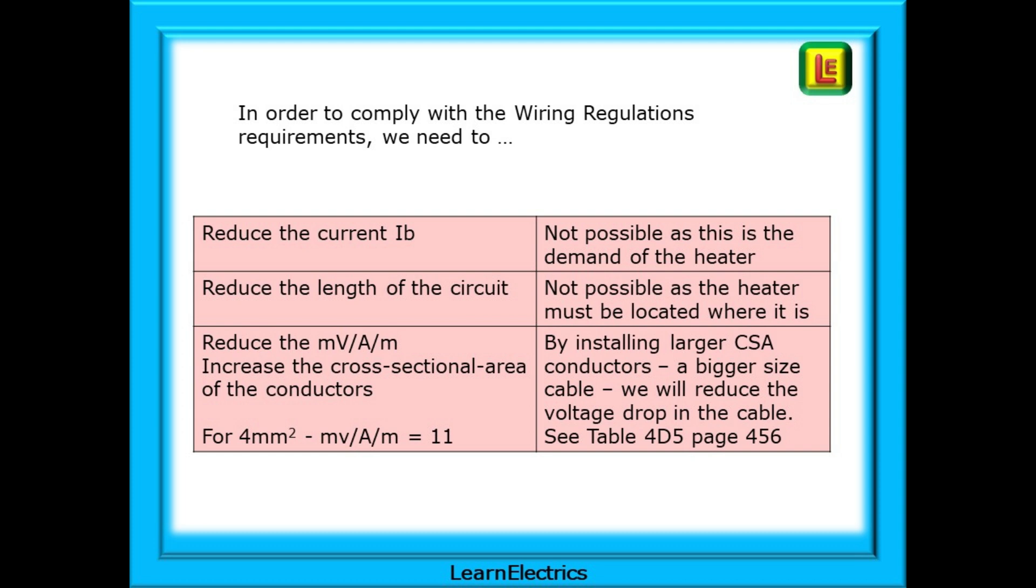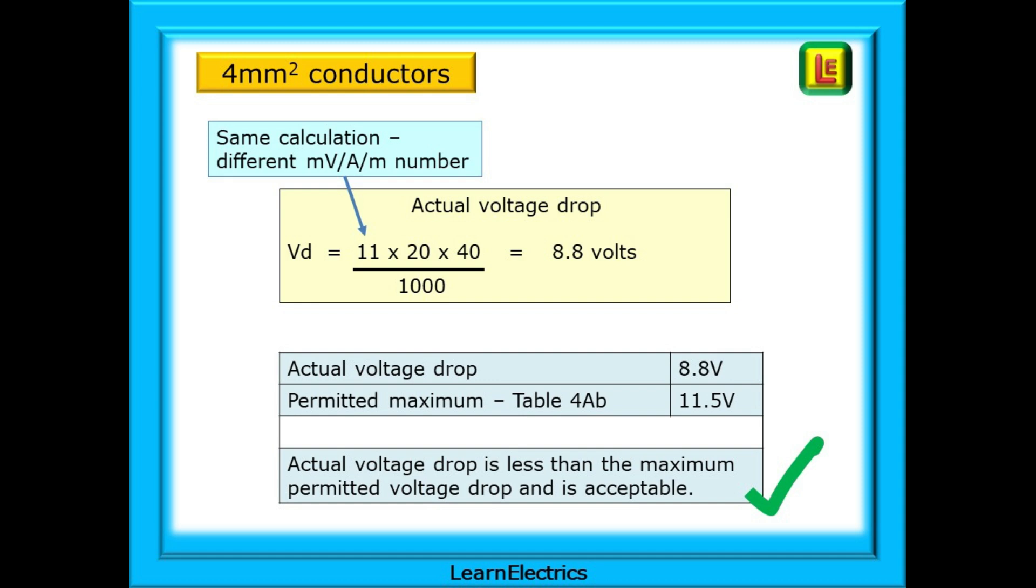Is it possible to reduce the MVAM number? Yes, it is. We can do this by increasing the cross sectional area of the conductors. By installing larger CSA conductors, a bigger size cable, we will reduce the voltage drop in the cable. See table 4D5 page 456 and find 4 millimetres on the left column. The corresponding entry in the rightmost column shows that for a 4 square millimetre conductor the MVAM is 11. Let's put that number into the calculation and see what answer we get. The same calculation but now with 11 for the MVAM number. This is a bigger cable size so the voltage lost in the cable will be reduced. Putting the numbers into a calculator we have an actual voltage drop of 8.8 volts for the 4 millimetre conductors. This is less than the permitted maximum of 11.5 volts and therefore an acceptable value for this circuit.